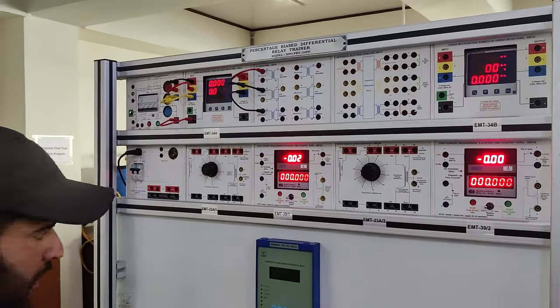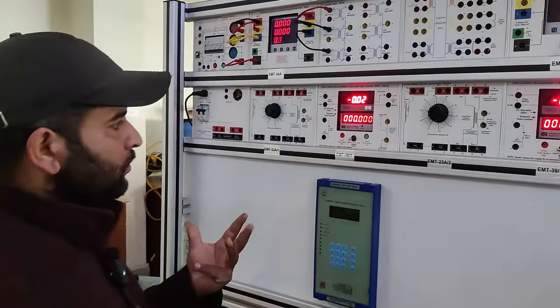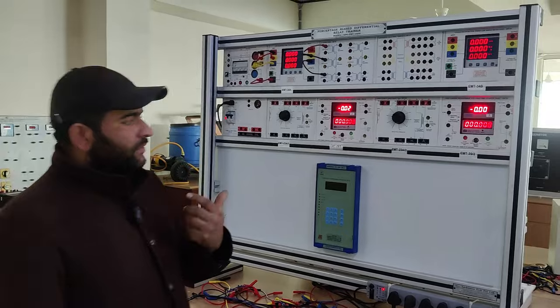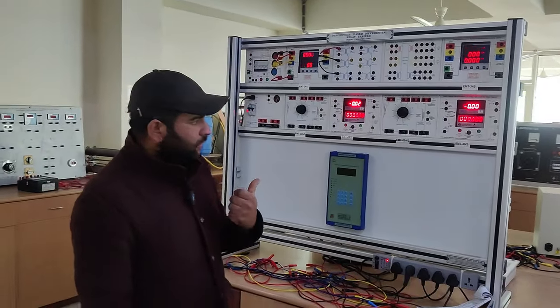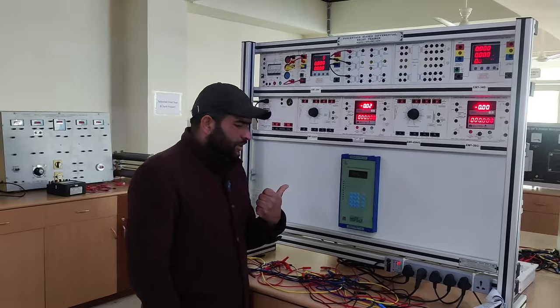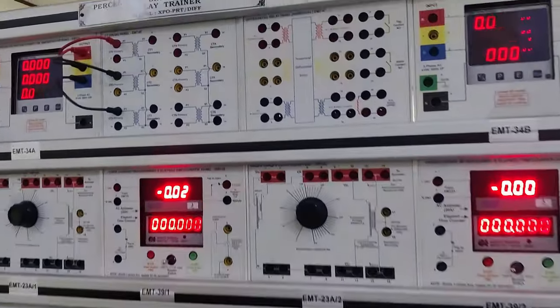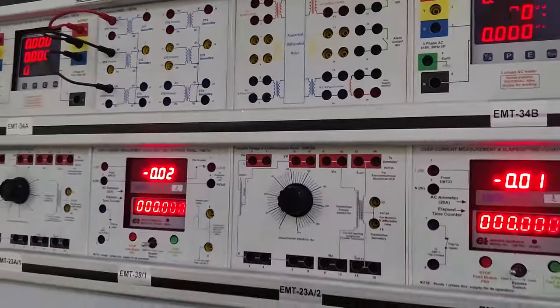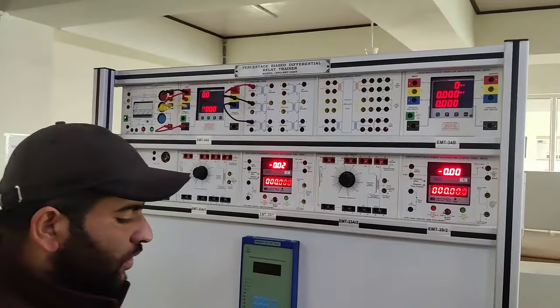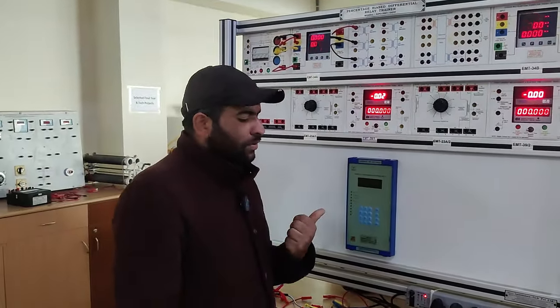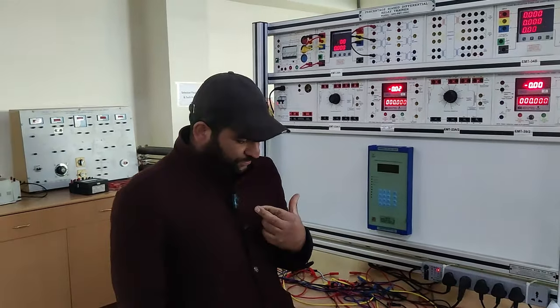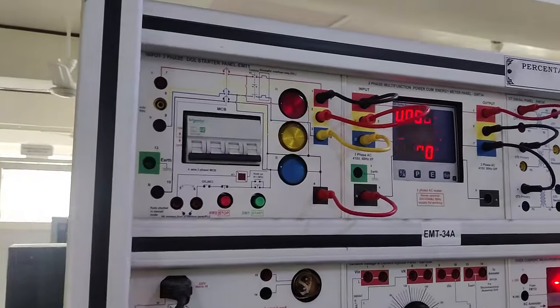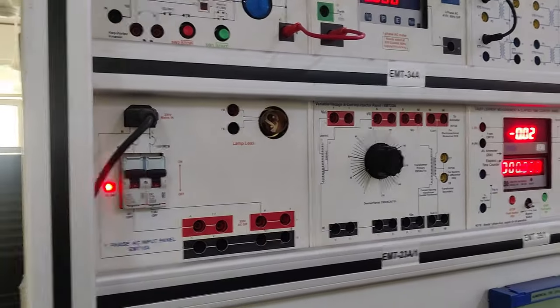We are going to show the basic operating characteristics of this relay. I will be plotting a graph between the restraining current and the differential current. The reason we shifted from electro-mechanical relay systems to numerical differential relays is that a numerical relay is a computer-based system with software-based protection algorithms for detection of electric faults. Such relays are also termed as microprocessor-type protection relays.